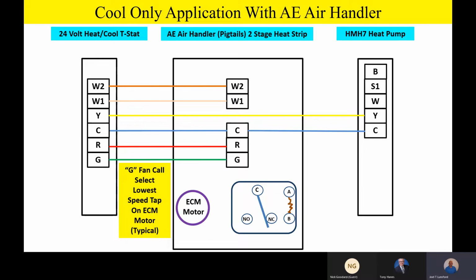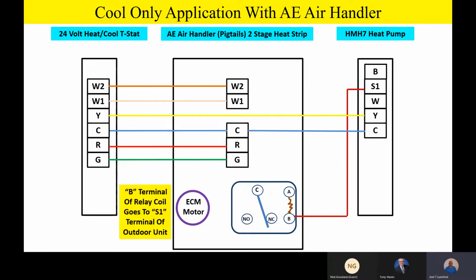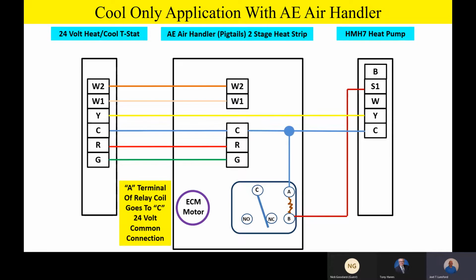Now, if you want to utilize on the AE air handler the airflow reduction circuit, we're going to do just like we did before. We're going to have that RV relay, or excuse me, the S1 relay. We're going to have that single pole double throw relay. We're going to hook the coil of that relay up to a 24-volt common and S1. The common terminal for the switching contacts is going to be going to the yellow wire, just like we had before for compressor operation.